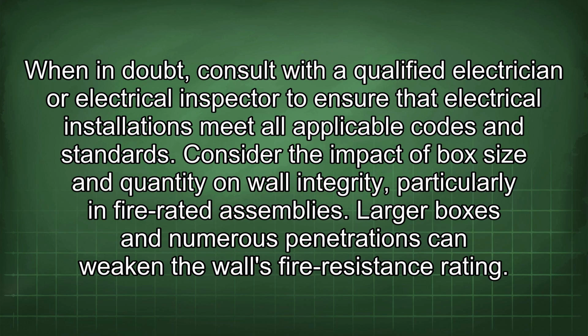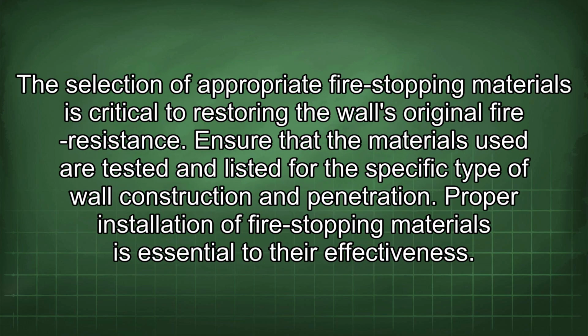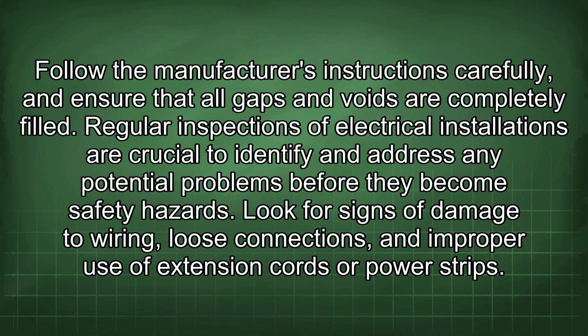and standards. Consider the impact of box size and quantity on wall integrity, particularly in fire-rated assemblies. Larger boxes and numerous penetrations can weaken the wall's fire resistance rating. The selection of appropriate fire-stopping materials is critical to restoring the wall's original fire resistance. Ensure that the materials used are tested and listed for the specific type of wall construction and penetration. Proper installation of fire-stopping materials is essential to their effectiveness. Follow the manufacturer's instructions carefully and ensure that all gaps and voids are completely filled.